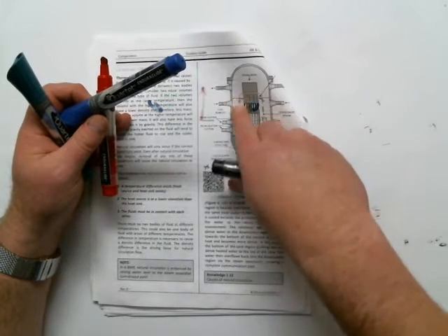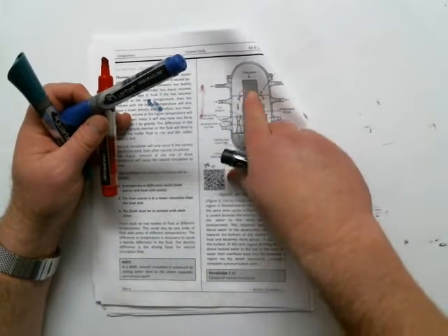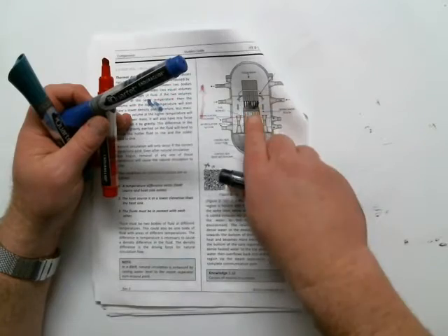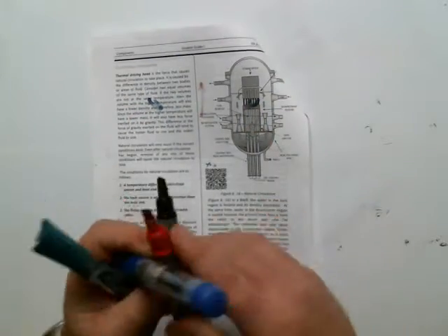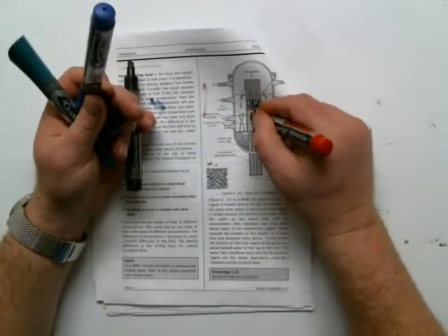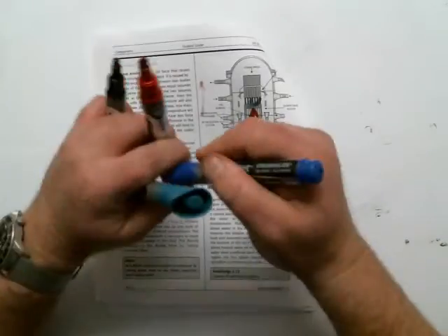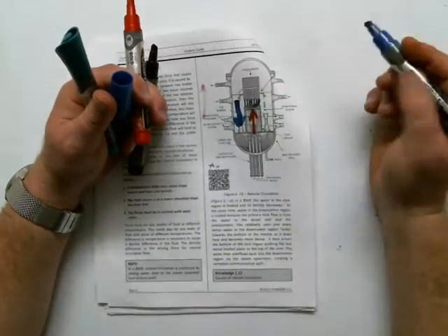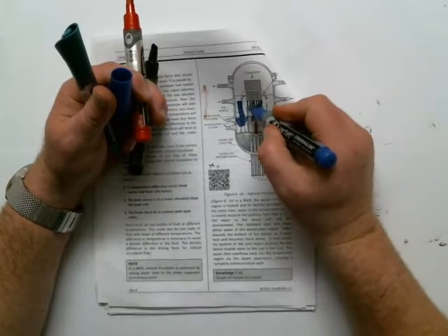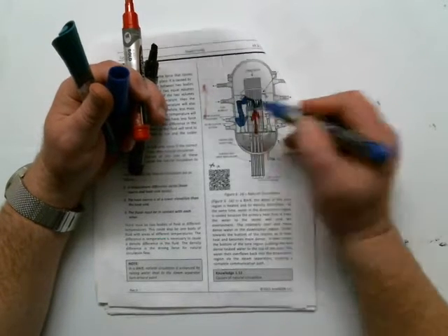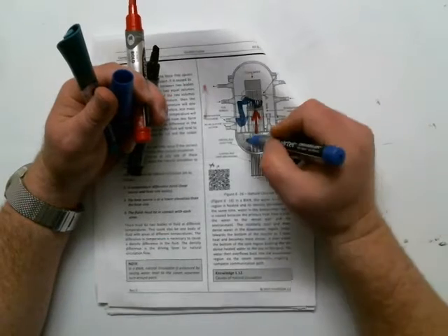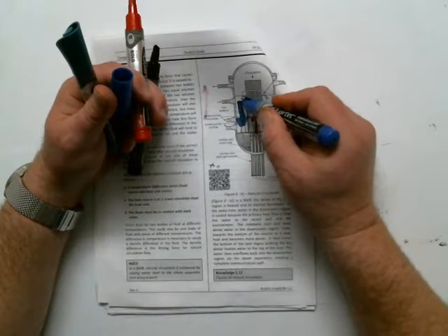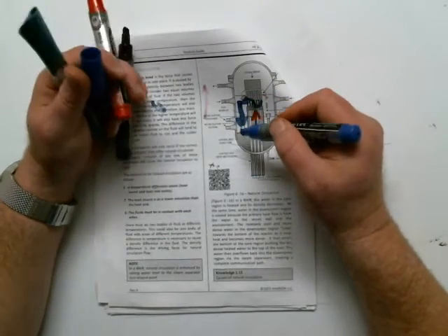Our cool water is out in the downcomer, and our warm water is in the core, the barrel region. It's going to tend to rise here. This is going to want to rise, and you see that. And then the water flow here in the cold path and the downcomer is going to want to fall. And the communication is from the dryers and separators here returning water. The warm water that comes this way will be separated and end up back in the downcomer.